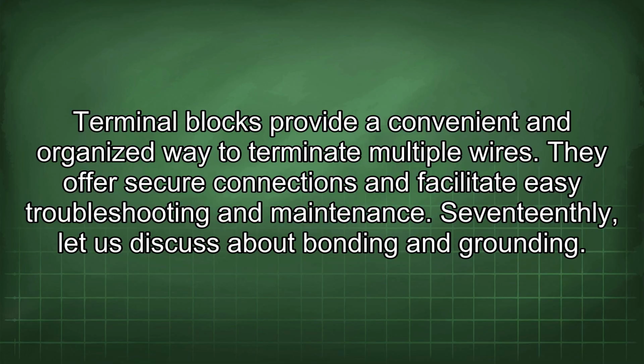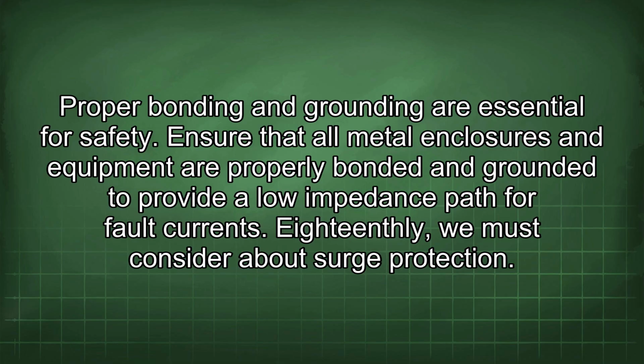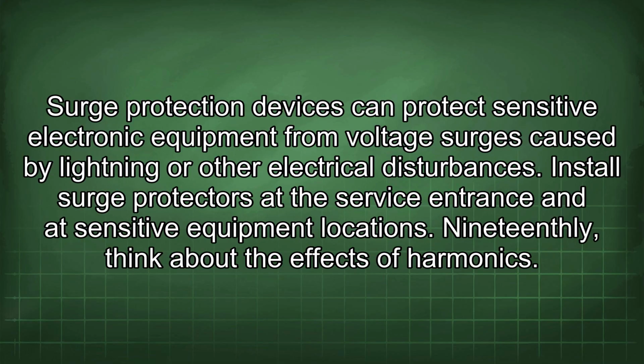17thly, let us discuss bonding and grounding. Proper bonding and grounding are essential for safety. Ensure that all metal enclosures and equipment are properly bonded and grounded to provide a low impedance path for fault currents. 18thly, we must consider surge protection. Surge protection devices can protect sensitive electronic equipment from voltage surges caused by lightning or other electrical disturbances.